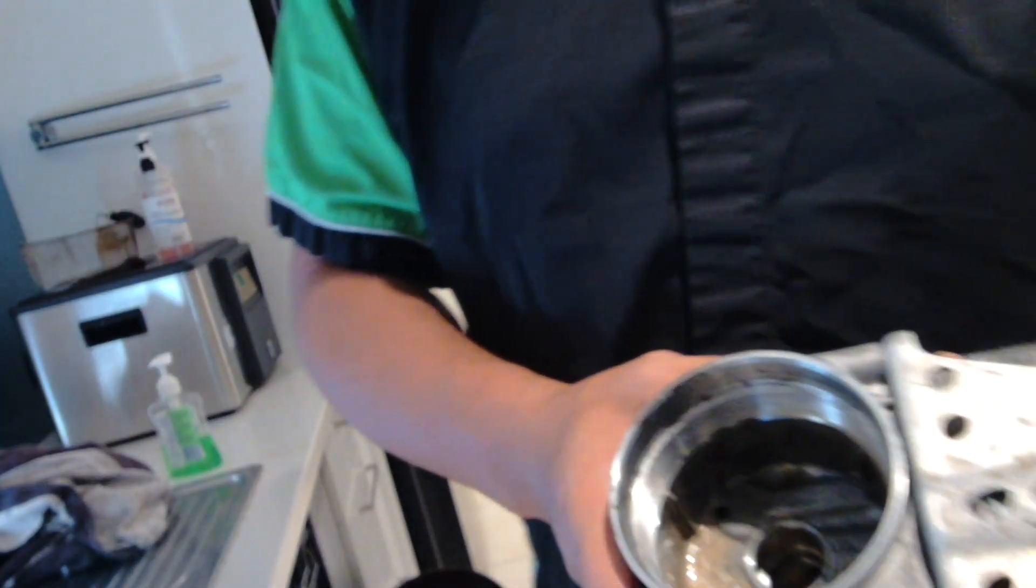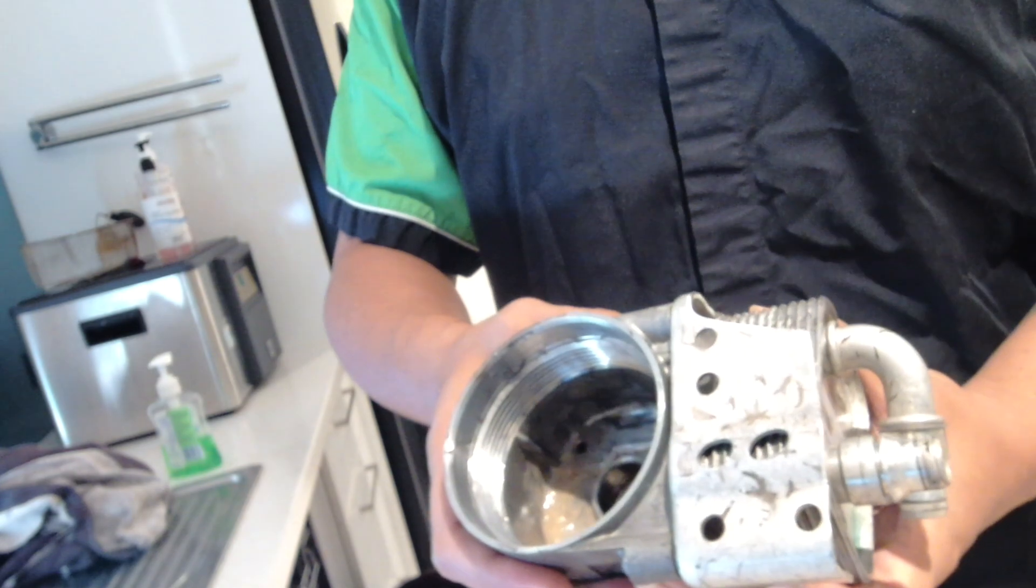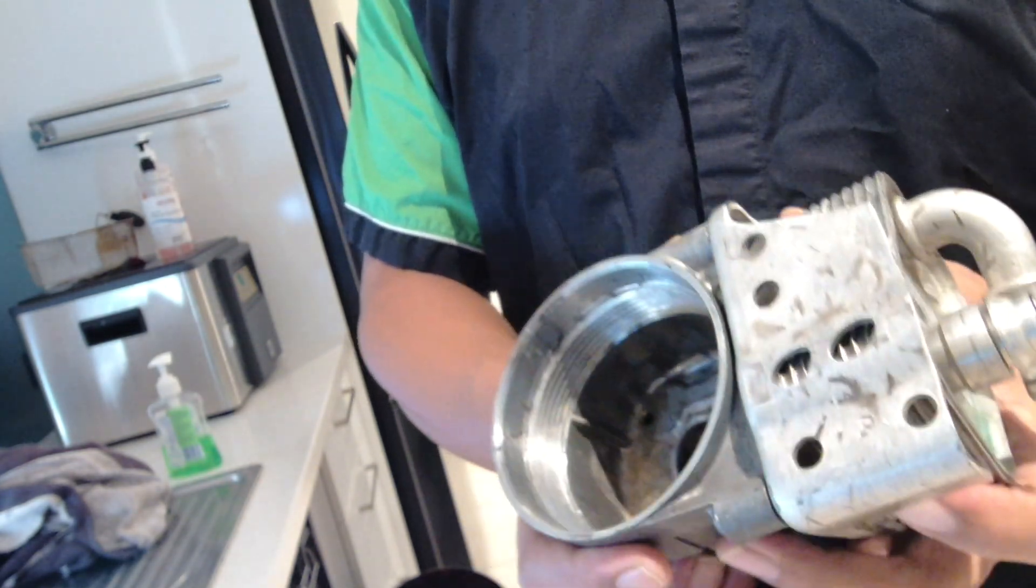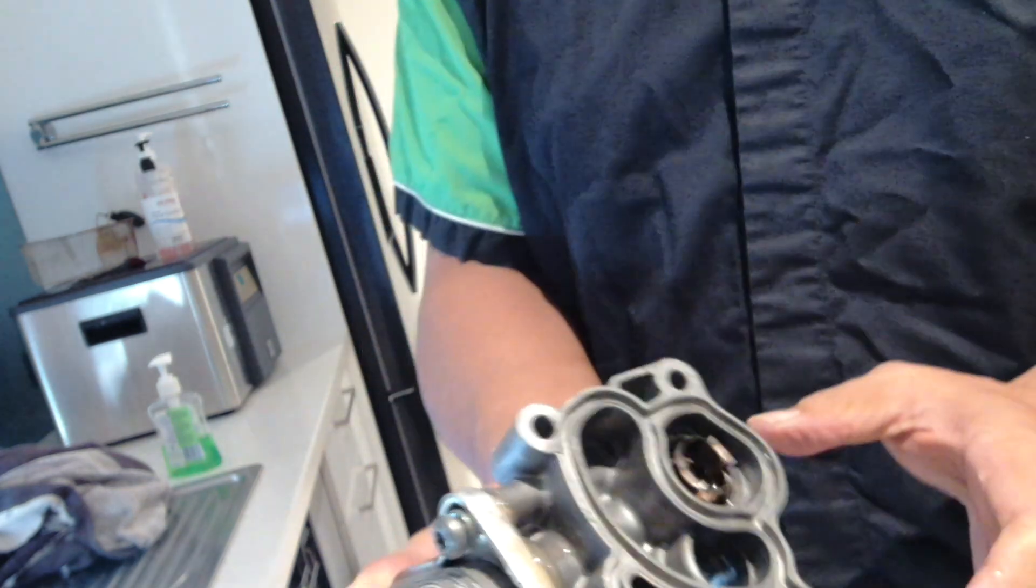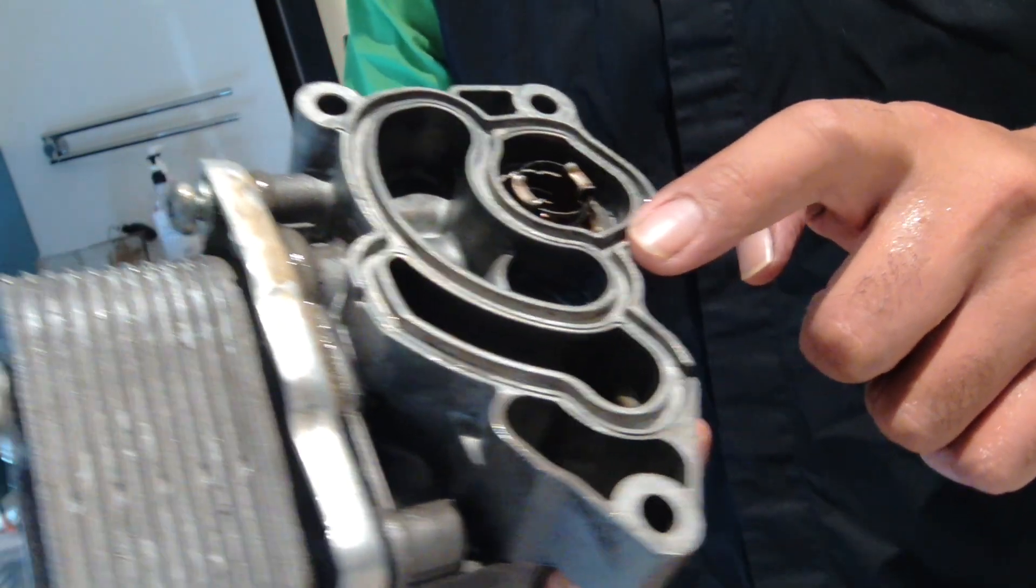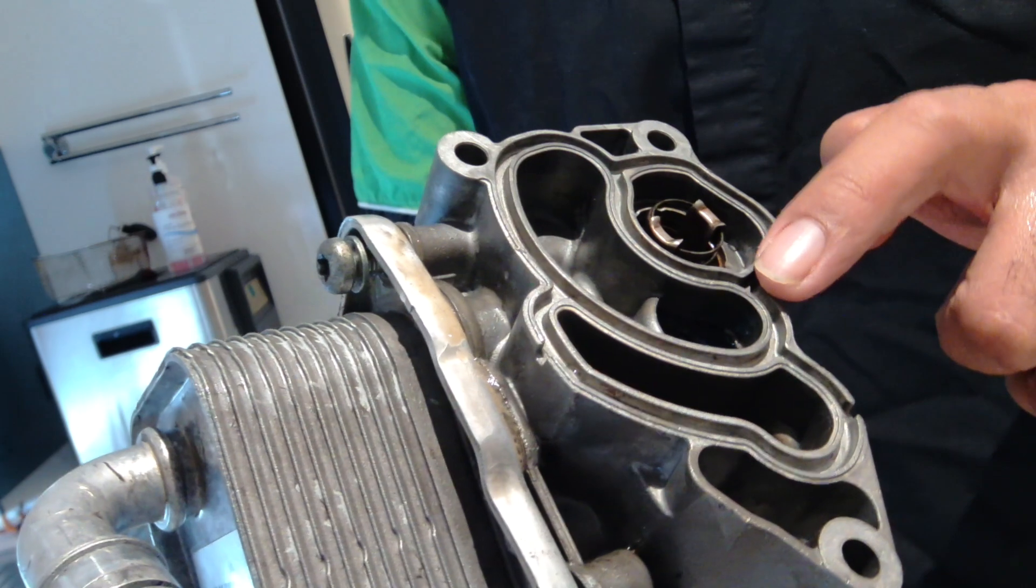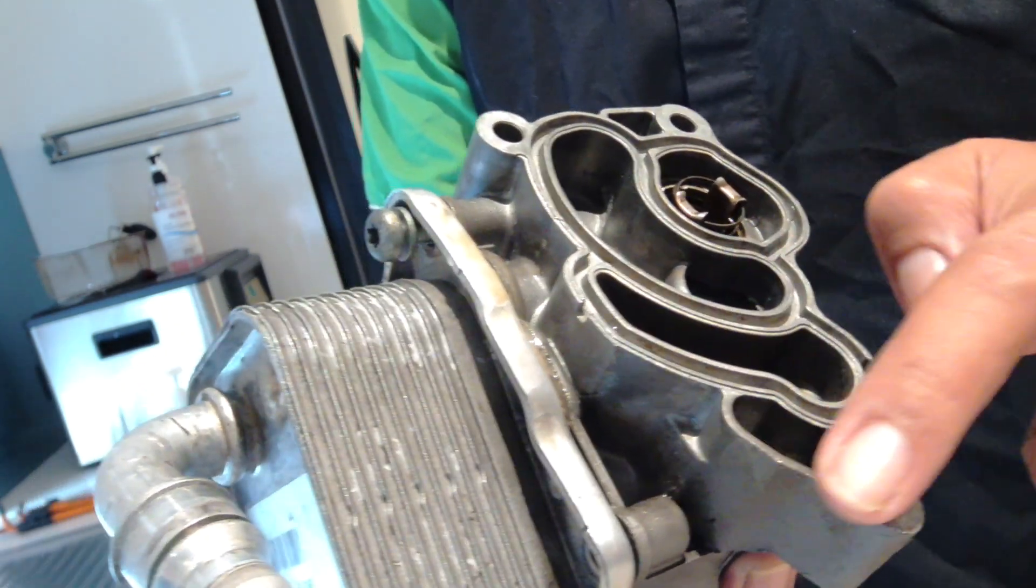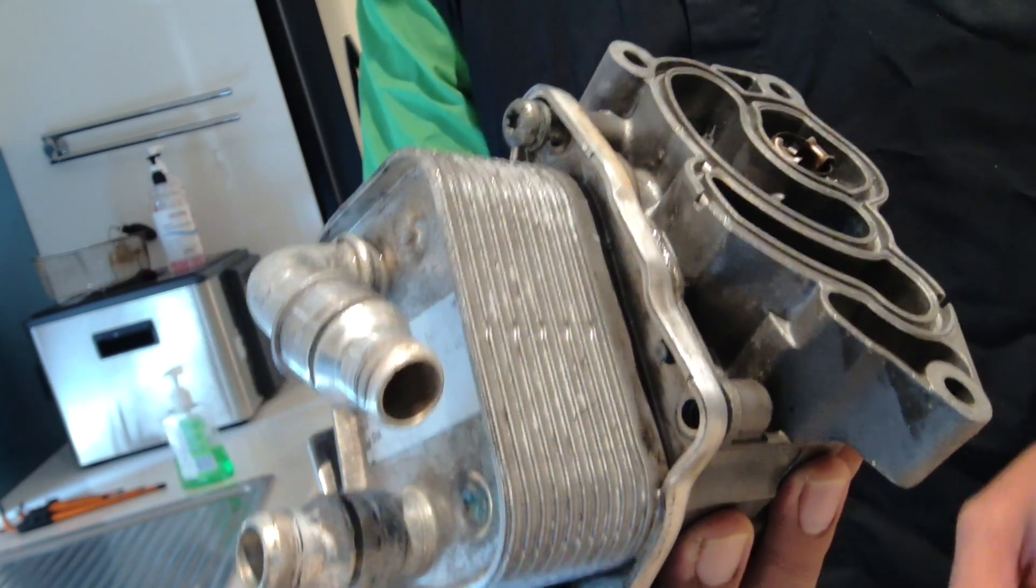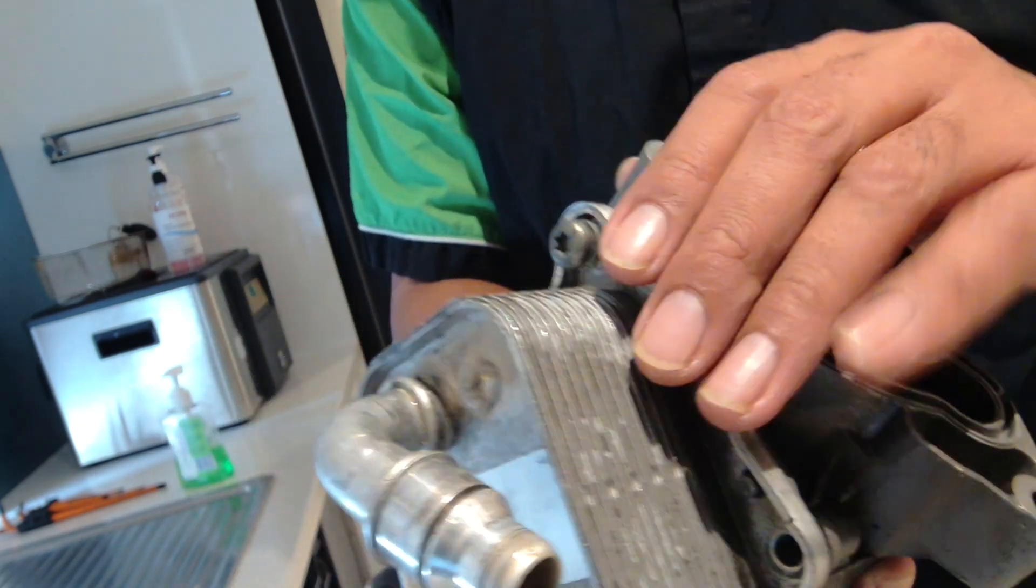Okay, so here's your exchanger here. The gaskets that we commonly replace is this one here. The chances of this one being affected by water is quite low. It's going to be on this side here, where the exchanger is, where the actual liquid and oil have a possibility of coming into contact.